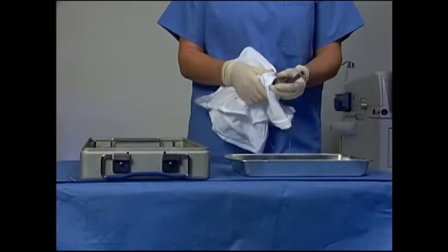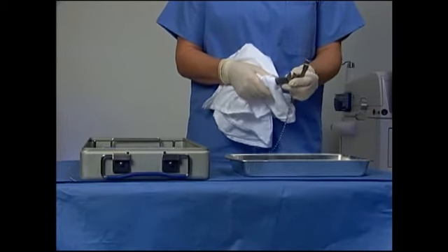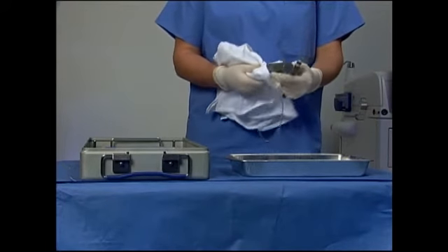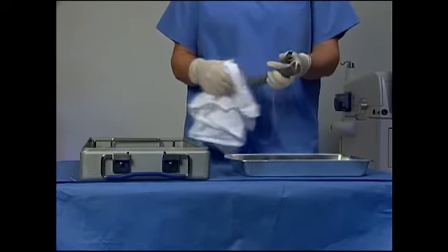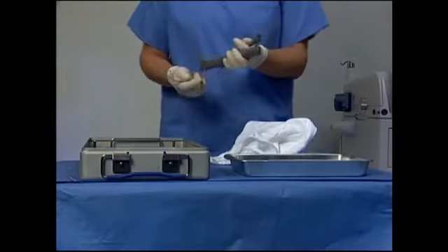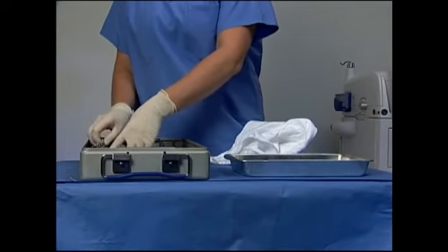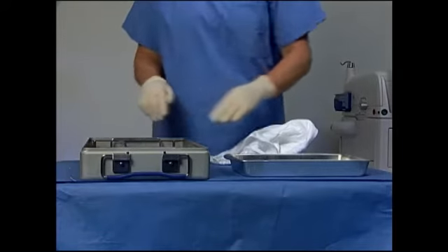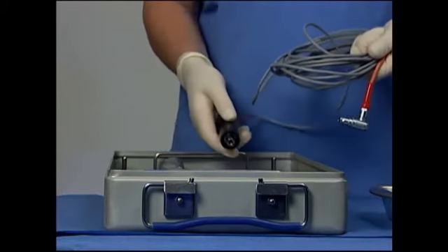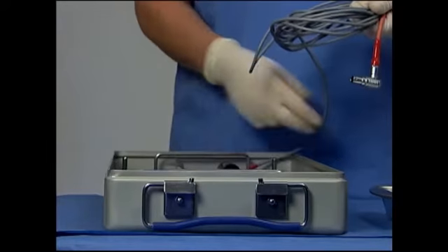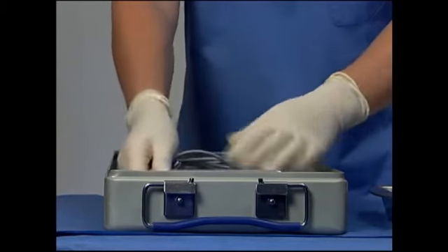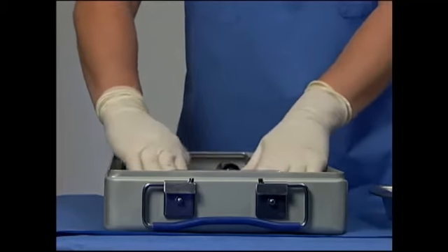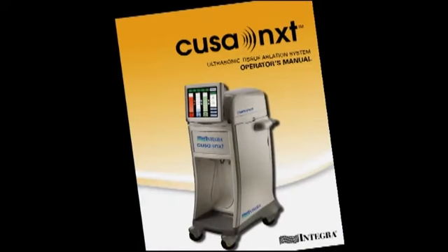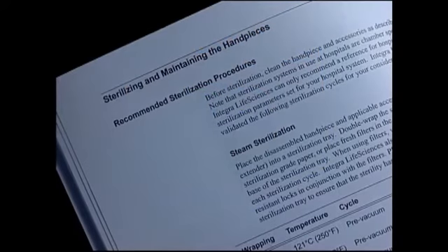Keeping the handpiece plug dry, rinse all parts in clean water and dry with a clean soft cloth. Clean the wrench set in the cleaning solution and then rinse it with clean water. Place the wrench set in the sterilization tray. Place the disassembled handpiece, angled extension, shroud, and wrench set in the sterilization tray. If using reusable tips, add a tip and flue to the tray. To sterilize the handpiece, follow the handpiece sterilization parameters as indicated in the CUSA NXT Operator's Manual.